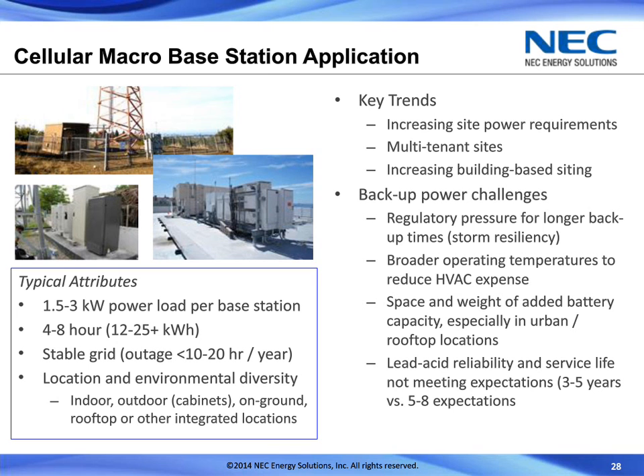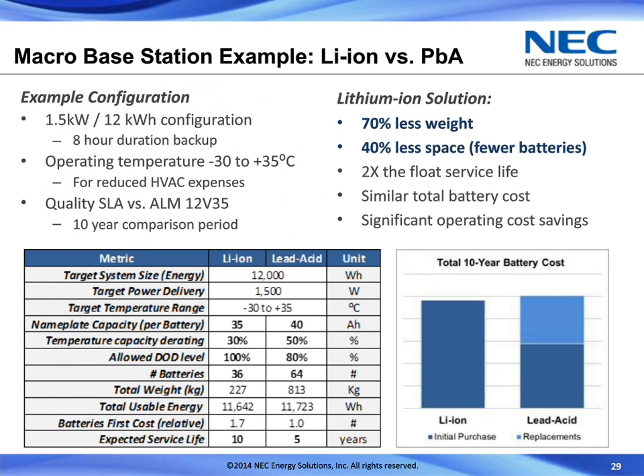So just going to take a closer look into some of the numbers. For this configuration, we chose 1.5 kilowatts, 12 kilowatt hour. So that's an 8-hour runtime. We're looking at minus 30 degrees C to positive 35 degrees C. And again, having the battery able to handle that temperature range allows you to reduce your HVAC expenses. And we're comparing a quality sealed lead acid battery versus our ALM 12V35 over a 10-year period.